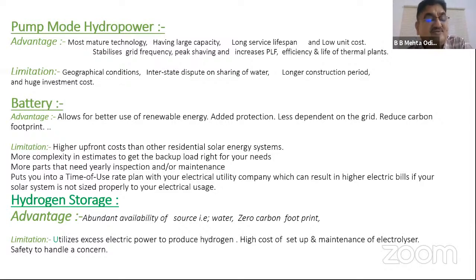It stabilizes grid frequency and peak shaving, so it addresses all the requirements of storage and balancing. There are some limitations too: it needs a specific geographical condition, interstate disputes on sharing of water, longer construction period, and huge investment. But if we keep the construction cost of the hydro project aside and only think of the delta component of providing pump mode, the cost of turbine is not making much difference. What is important is you need a small dam at the tailrace to store the water going out and bring it back instead of letting it run away to the sea. So that cost has to be accounted for.